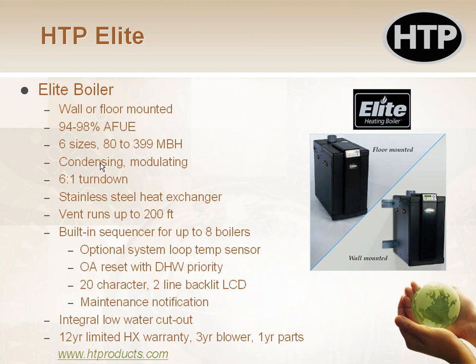On the commercial projects, this one has built-in controls that do outside air reset, like the other one I showed you, the Munchkin Contender. Every condensing boiler I'm going to show you today does outside air reset, because there's no point in buying a condensing boiler and not allowing it to condense. And putting out 180 degree water is not going to allow you to condense. You've got to get that water temperature down below, say, 130 to get into a condensing mode. So on mild days when it's 40, 50 degrees outside, we need to keep that water temperature set point low, say 110 to 130, in order to get into condensing mode. But if it's really cold out, like -10, that design day that almost never happens, go ahead and let it ramp up higher if we need to, up to 180 or whatever we need.